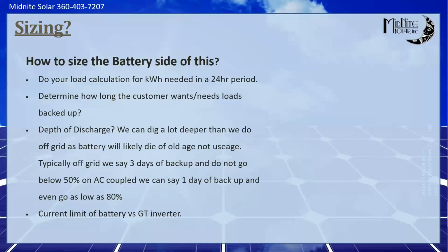And then, the current limit of the battery versus the grid tie inverter is another thing to look at. So what I mean by that is, let's say in step 1, the customer determines they only want 6 hours of backup, and your math says they only need 4 kilowatt hours of battery. So you're like, perfect, I'll throw a PowerFlow 5 in there. I've got 5 kilowatts of battery backup. I've got a Rosie. I've met the customer's needs 100%.